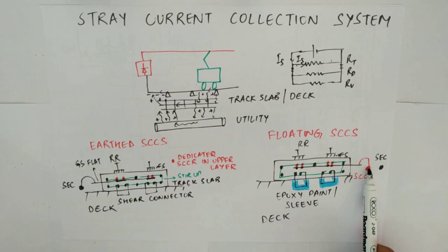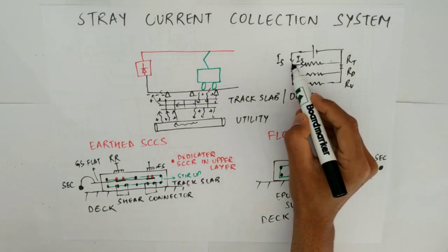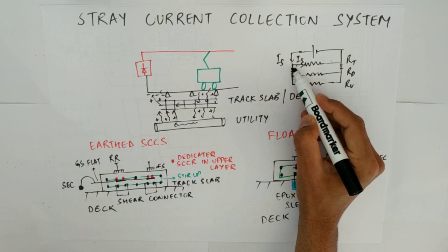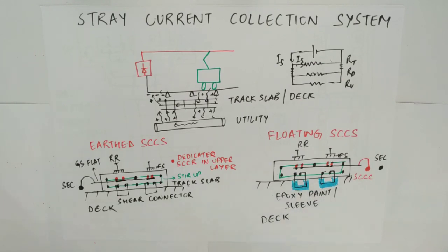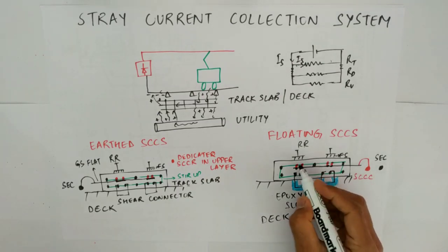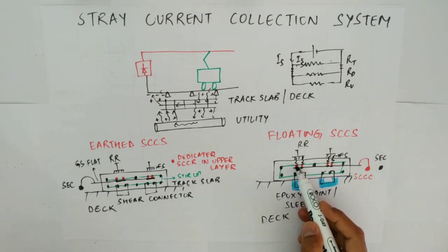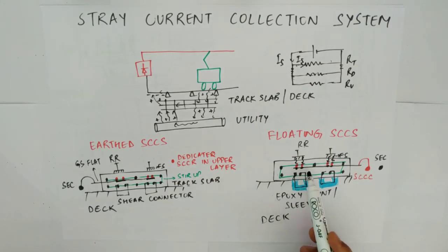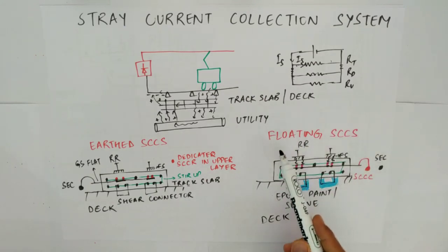This SCCC must be an insulated cable. From here there are some shear connectors which are connecting the track slab to the deck reinforcement. So you are trying to offer high impedance here — by offering high impedance you need to insulate, so you either provide an insulating sleeve or you do an epoxy paint to these shear connectors. By doing this, the current will flow in this path and when it tries to find another low resistance path below, it cannot go because it is insulated — so the current remains in the track slab itself and does not hurt the other utilities. This is why we provide this stray current collection system.